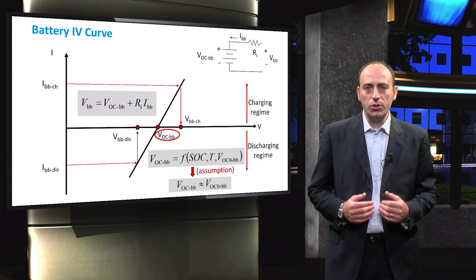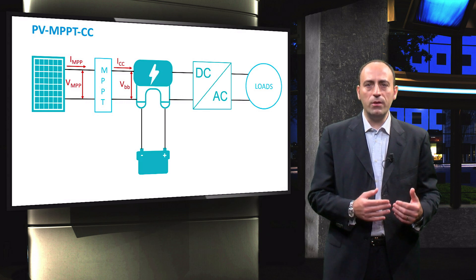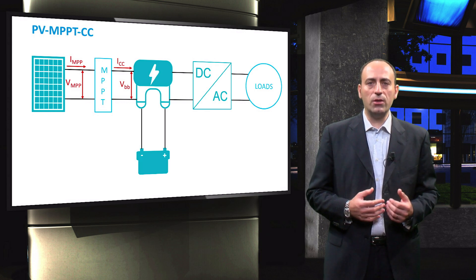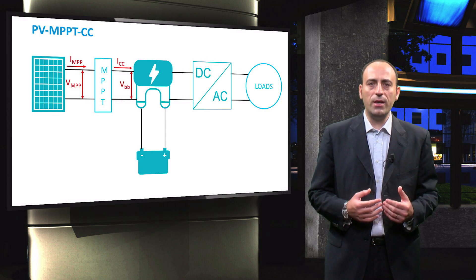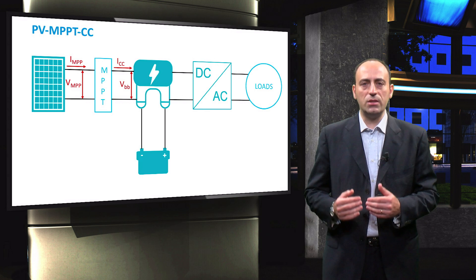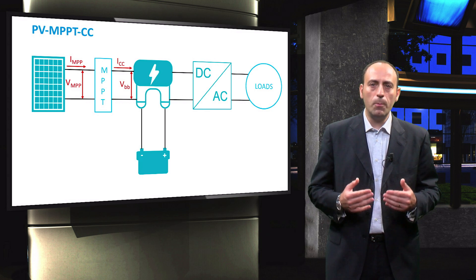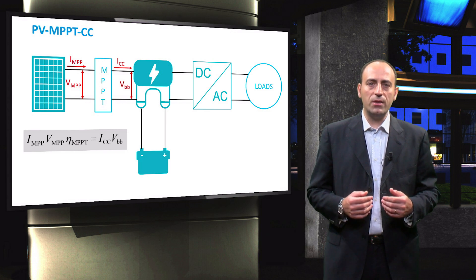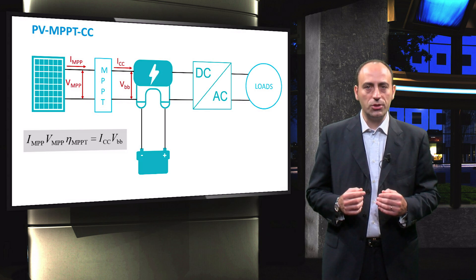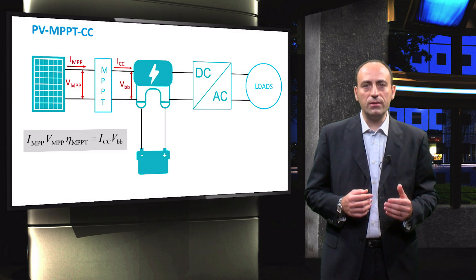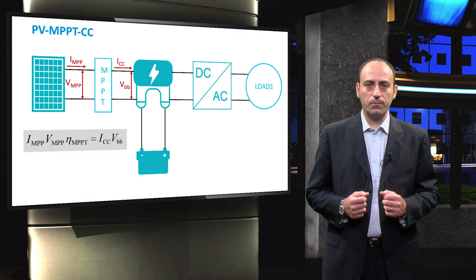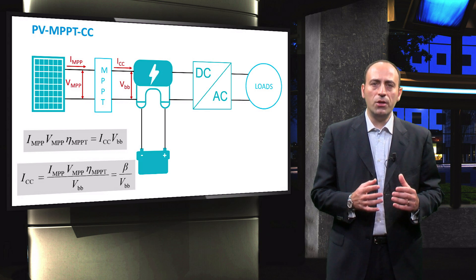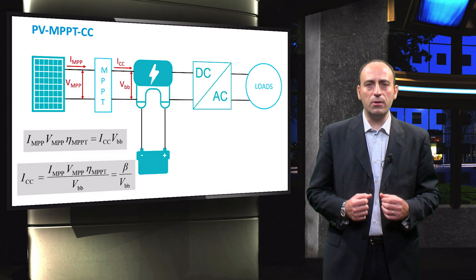Going back to the topology of the PV system, let us look at how the power is transferred from one component to the other. First, we start by looking at the left-hand side of the system topology. Here, the power generated by the PV modules, derated by the efficiency of the maximum power point tracker, is equal to the power received at the input port of the charge controller. From this equation, an expression for current entering the charge controller ICC is obtained. To simplify the calculations in the later stages, the numerator of the ICC equation is represented by a variable beta.